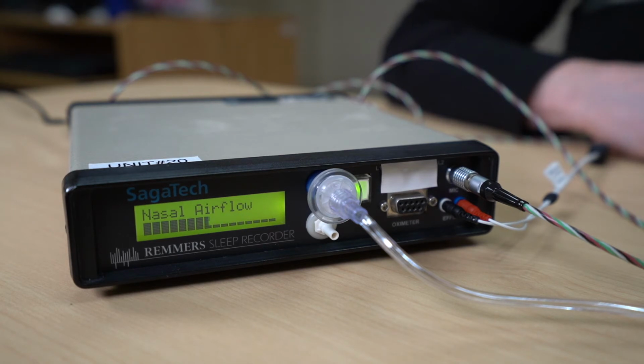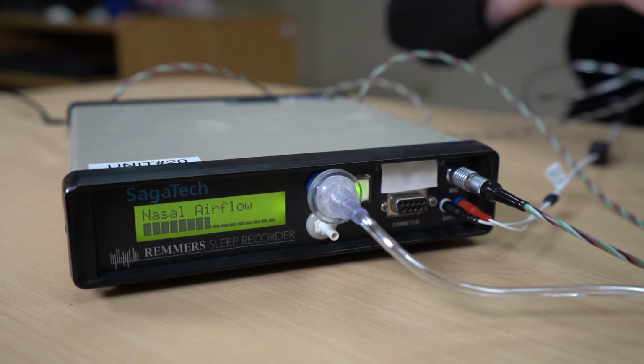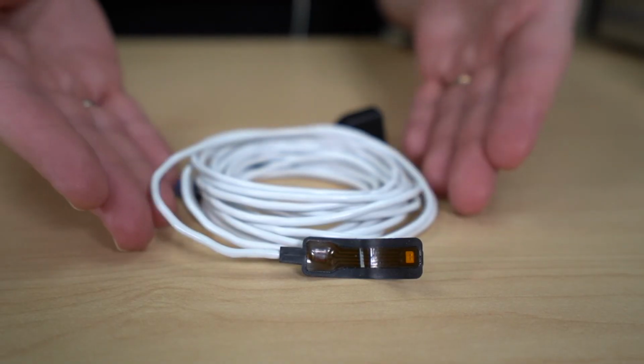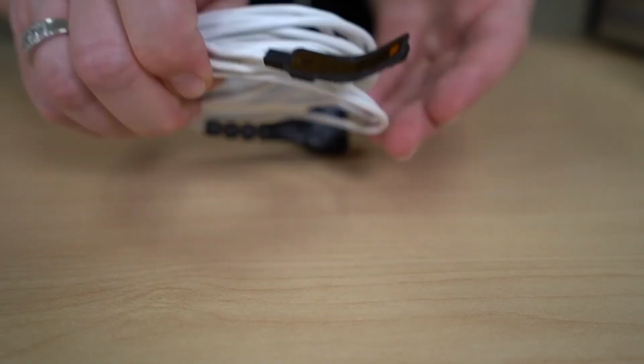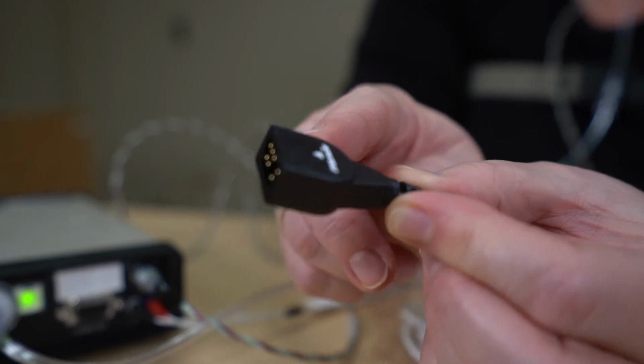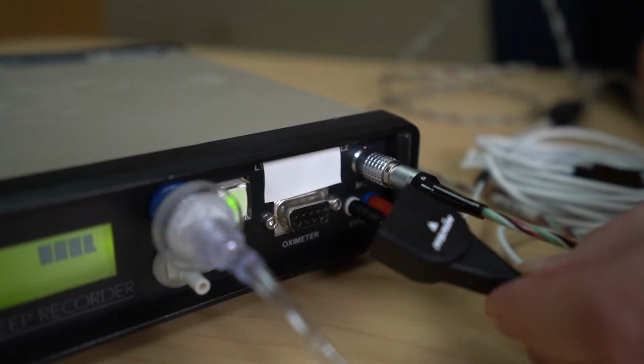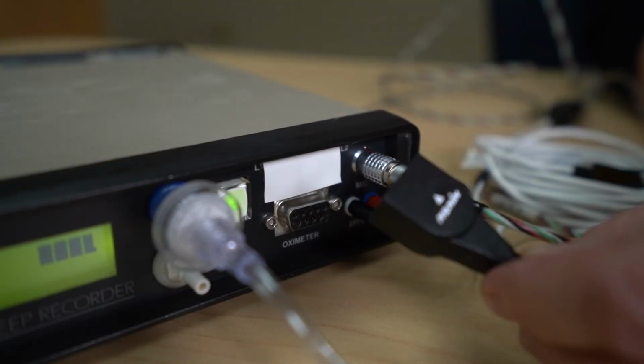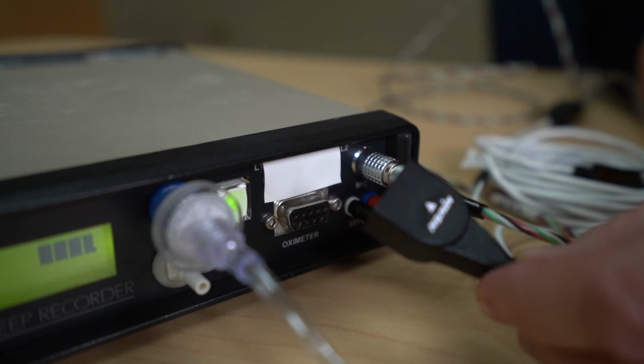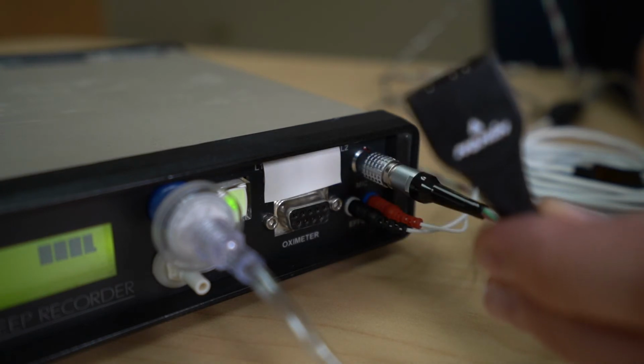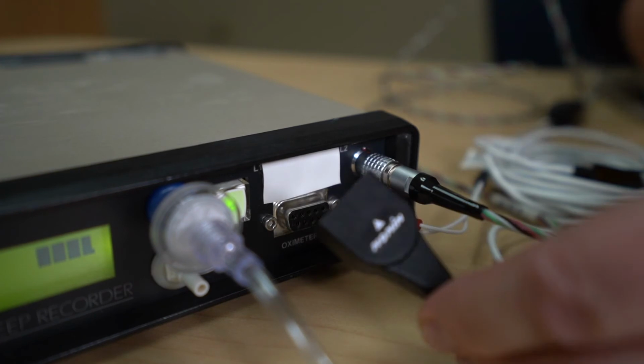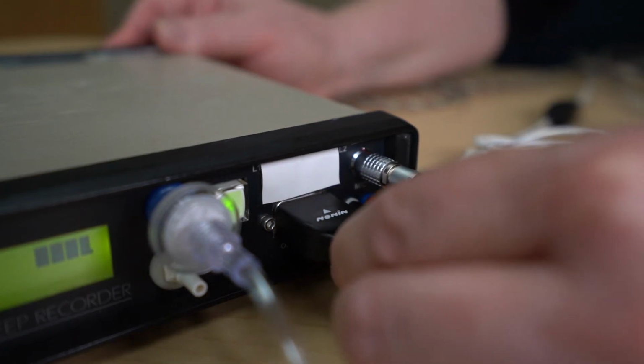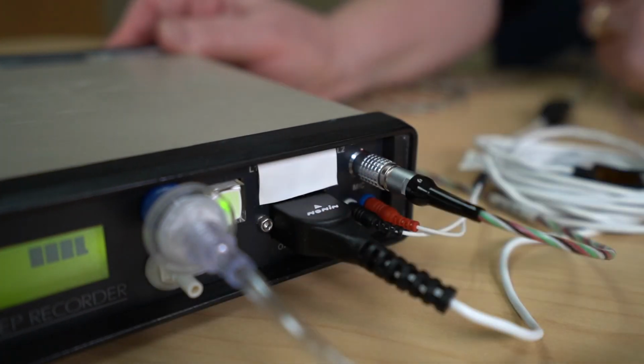Take a couple of breaths through your nose. You will see the bar graph indicators moving back and forth with your breathing. Our last accessory is the oximeter finger probe. The finger probe attaches to the recorder using a serial port type of connector. Locate the oximeter port on the recorder. Insert the connector into the recorder with the white writing on the probe connector facing up.